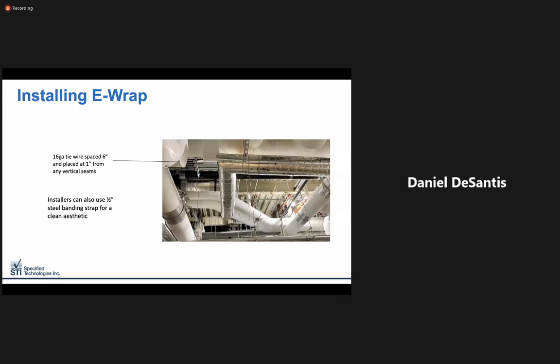As mentioned, EWRAP is applied in layers corresponding to the desired hourly rating. For smaller conduits, size 4 inches and down, 5 layers are required for a 2-hour rating. Conduit greater than 4 inches in diameter only requires 4 layers to achieve a 2-hour fire resistance rating.